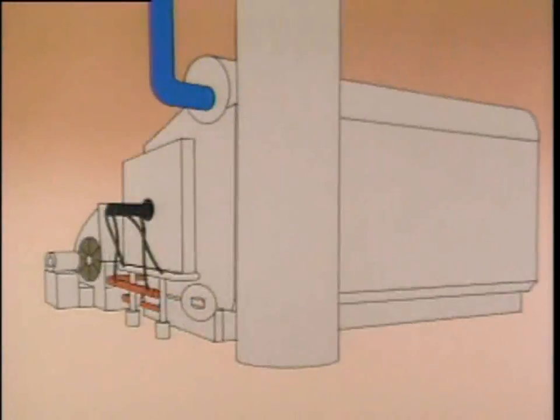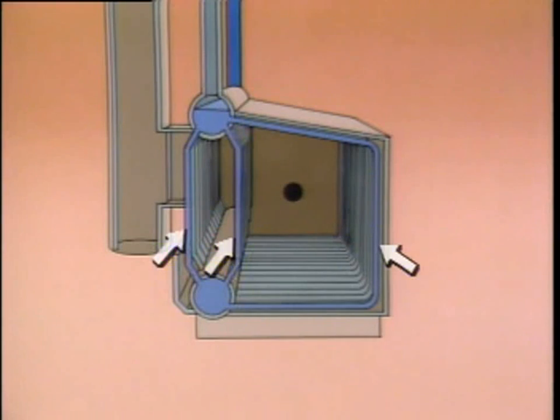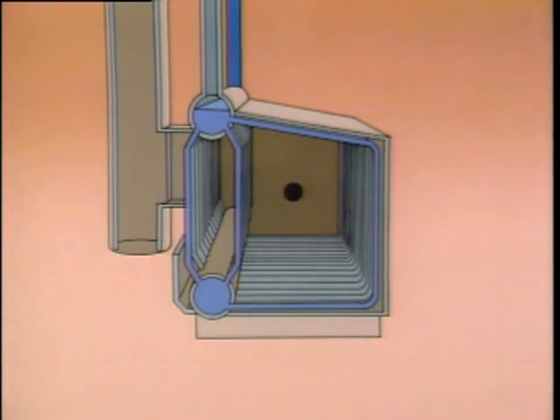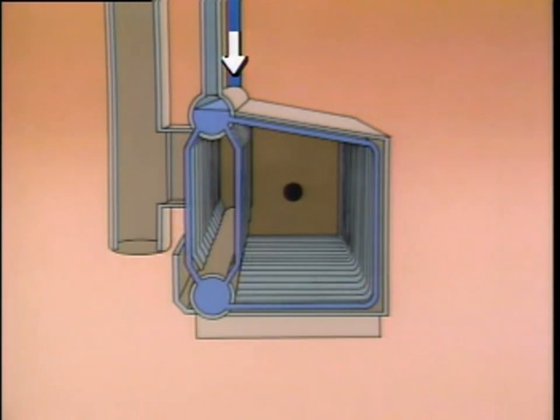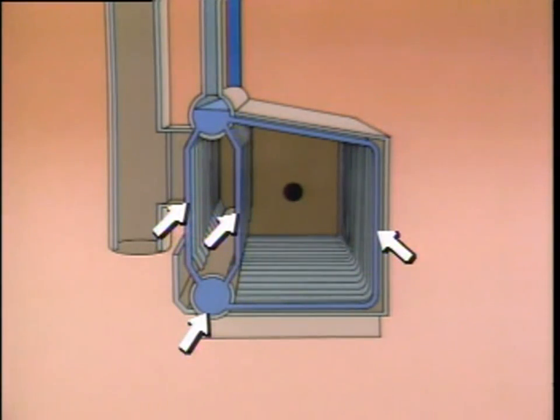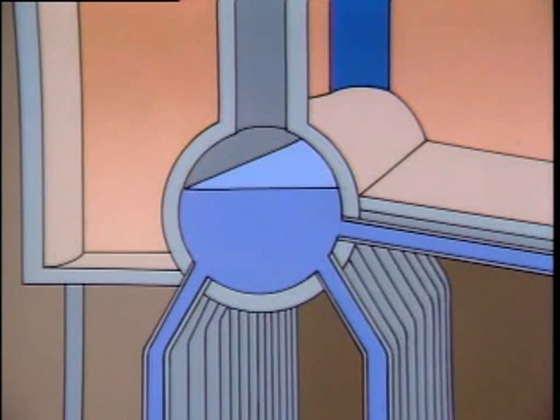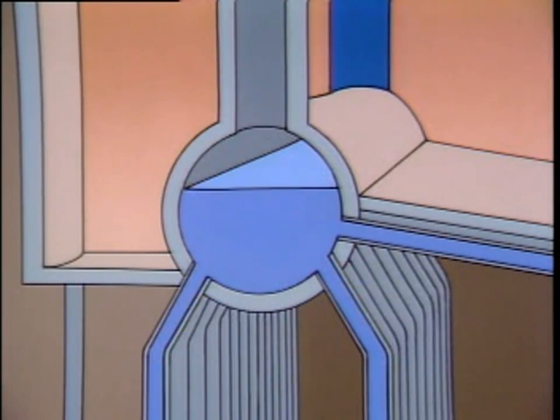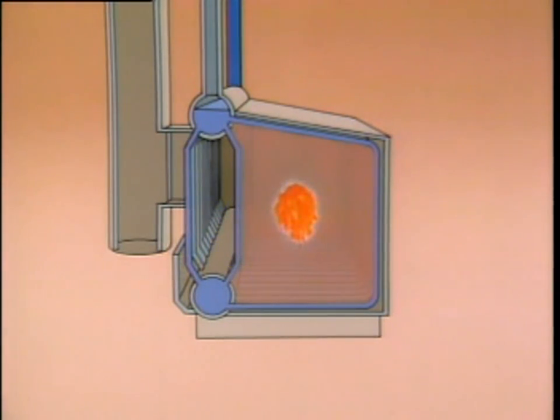Water tube boilers use tubes to route water and steam through the boiler, with combustion gases flowing past the outside surfaces of the tubes. This particular boiler consists of a series of water tubes and two drums that distribute water to the tubes. The water tubes connect the drums and form a wall around the combustion area where heat is generated. Water is fed into the upper drum through a feed water inlet line. The water tubes and the lower drum are completely filled with water, while the upper drum is only filled to a certain level, providing space for steam to collect — so it's often called the steam drum. As fuel is burned in the combustion area, heat is transferred to the adjacent water tubes.